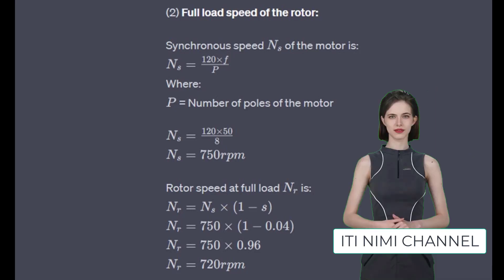To find the rotor's full load speed, we consider the slip. The formula is: rotor speed equals synchronous speed multiplied by (1 minus slip). This calculation gives us a rotor speed of 720 RPM.